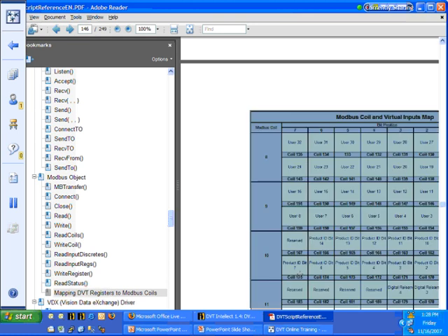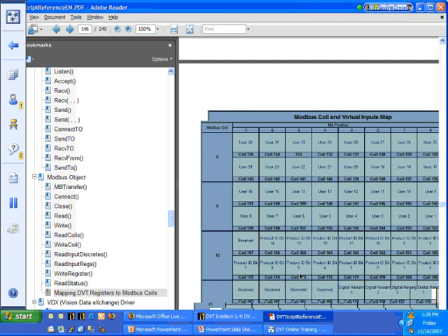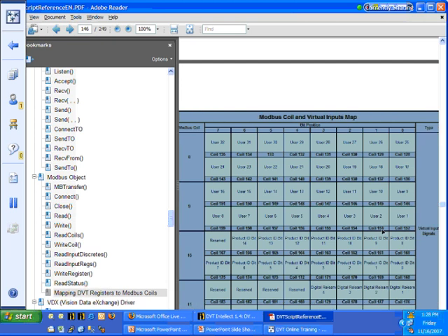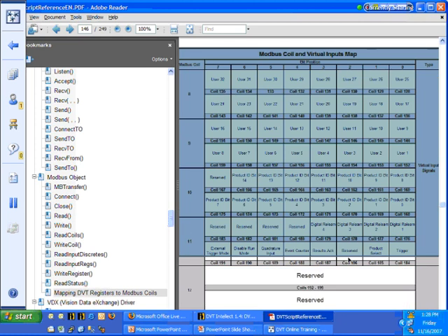let me zoom in on this a little bit, what you can view is the register mapping. And let's see if we can scroll this over some. This is the ModBus register mapping, and these are the input signals for that register map. You can see that at register 11, what we have is the trigger bit at the very first bit. So if I write to register 11 a value of 1, then I'm putting a bit high here and all these others low.